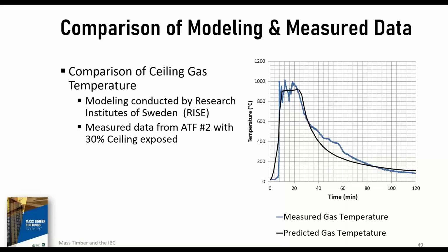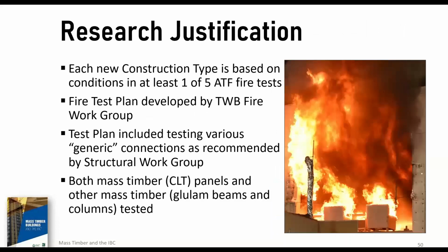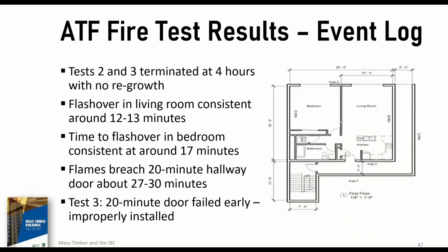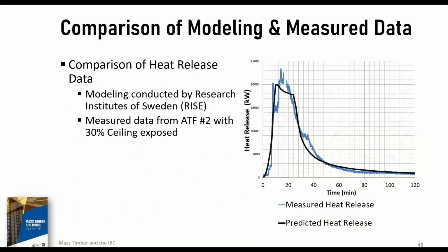So when we start talking about these values and these figures, I'll go back to this previous slide here. Heat release rate. So the megajoules per square meter anticipated design value was 550 megajoules per square meter, slightly hotter at 570 megajoules per square meter. The fire protection engineers tell me that a 500 kilowatt campfire is something you physically cannot stand next to. You have to back away from a 500 kilowatt campfire.